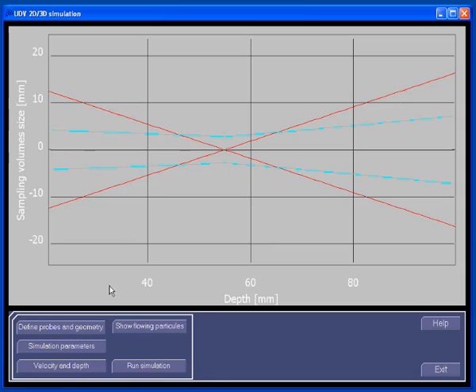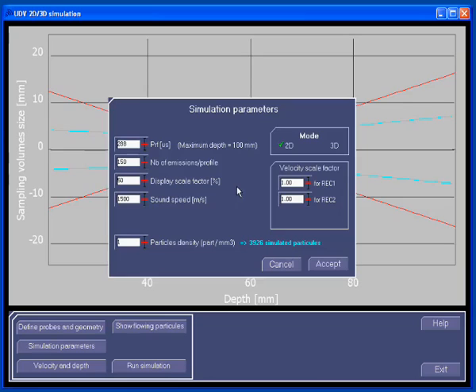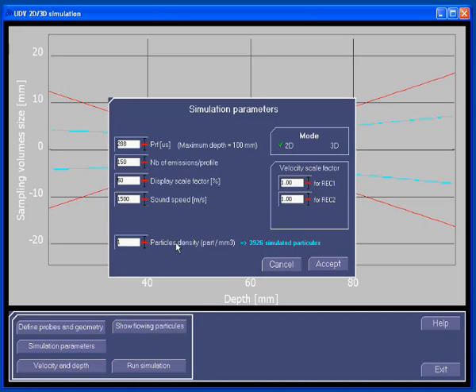Let's have a look at the simulation parameters. In this panel, you can choose between the 2D mode or the 3D mode. Two parameters are specific to the simulation: the display scale factor, which allows extending the velocity scales to improve visualization, and the particle density, which allows defining the amount of particles used for simulation. The number of simulated particles should be selected in order to have about a few thousand particles. All other parameters are common UDV parameters.